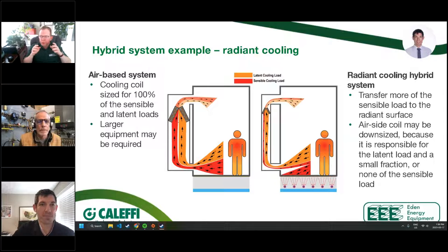Now, one of the things worth mentioning here, the thing that terrifies me the most would be somebody telling me that they're going to apply what you just said into an existing hydronic system. So let's say I've got my house from the 80s. I've got radiant tubing throughout. And Bob, I'm going to fill chilled water through that slab. Why don't you just walk through why that's terrifying?